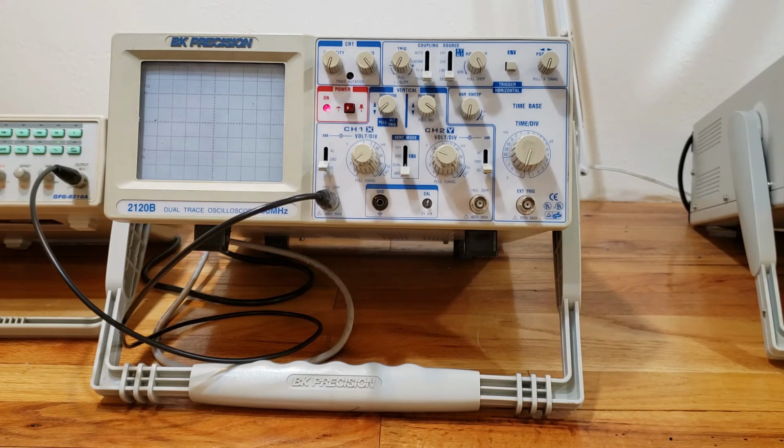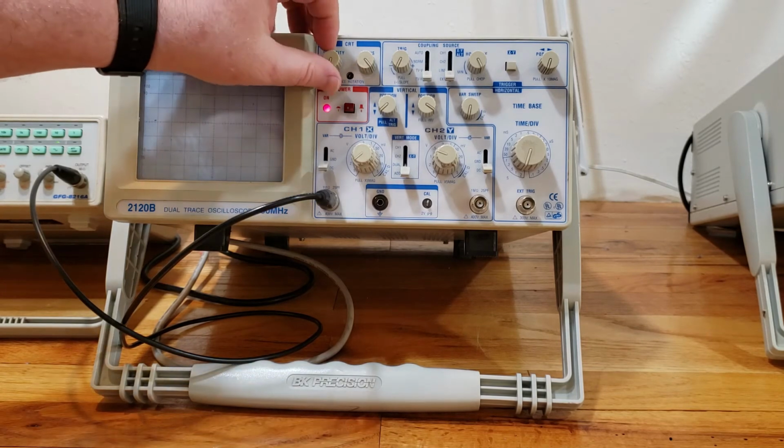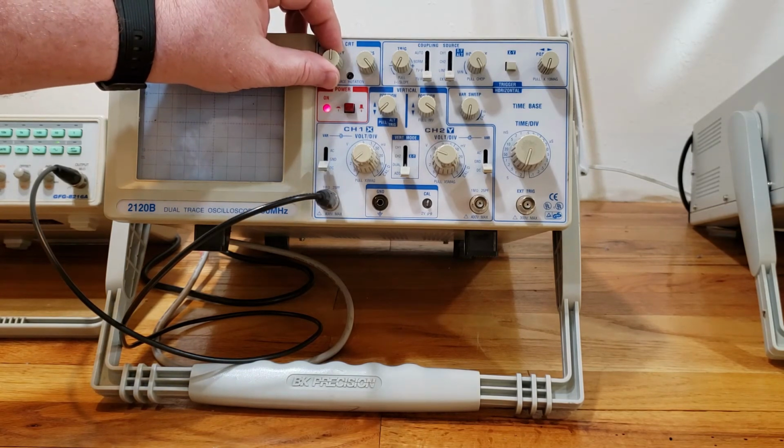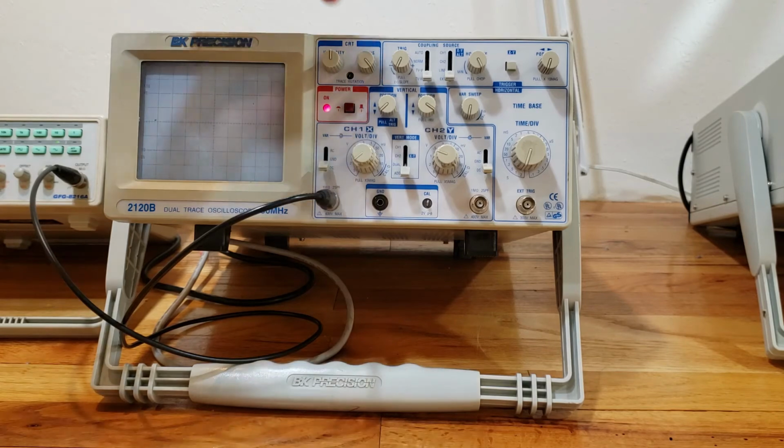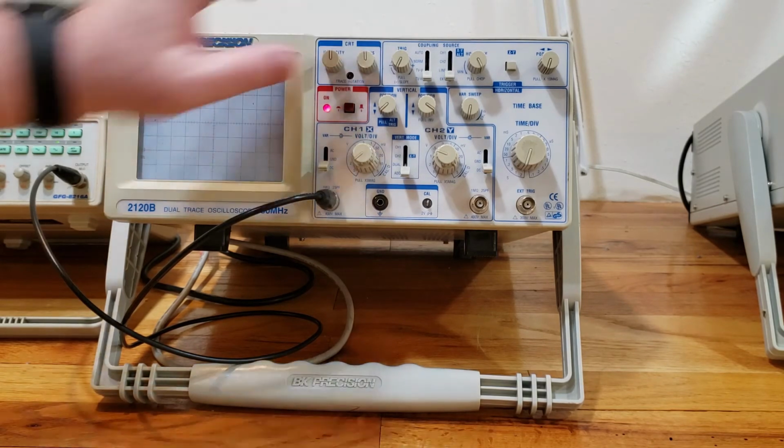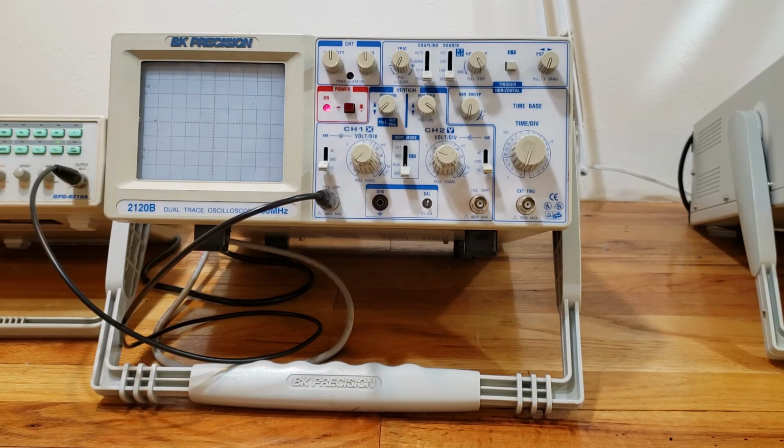And it always happens. So, starting in the upper left-hand corner with the intensity knob, if you look at your drawing, it has the indicator pointing straight up and down, just like I've got right here. We're going to call that position centered. So the intensity knob is going to be centered. The next thing we're going to do, working systematically across the top row, is take the focus knob and center it.